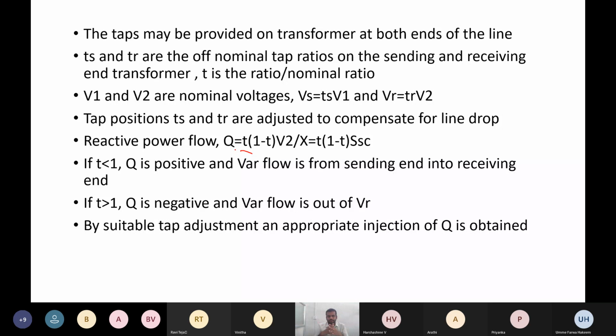So what is meant by T? T is the nominal ratio. So if it is less than 1, then reactive power will be sent from sending end to receiving end. And similarly, if T is greater than 1, at that time Q is negative. Negative is nothing but reactive power being drawn into our circuit, that is, from receiving end to sending end. So by using suitable tap adjustments, we can inject the Q. Q is our reactive power.